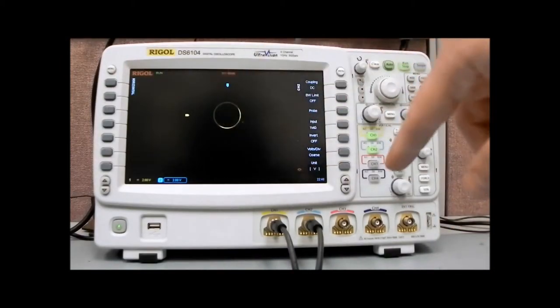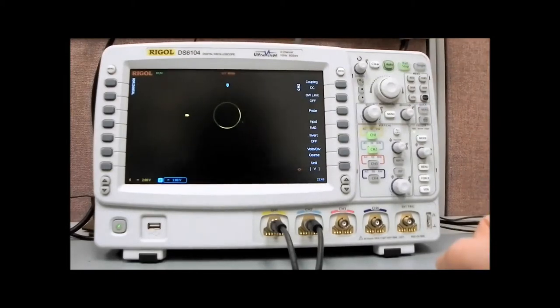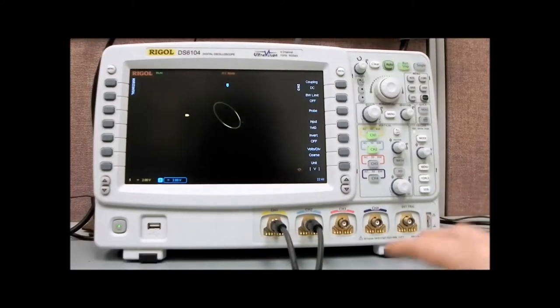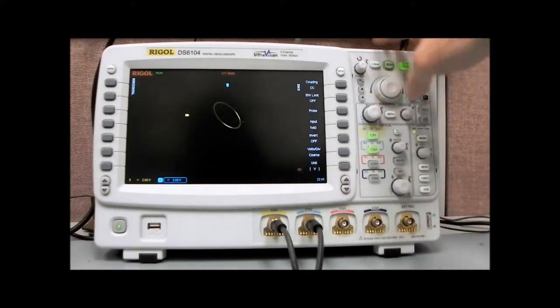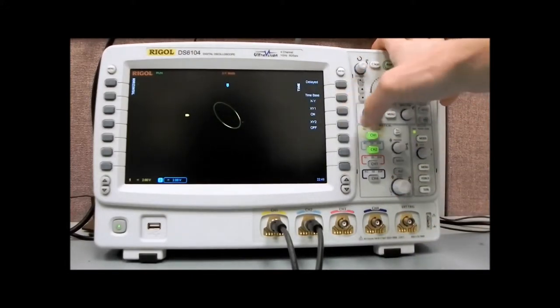So we're plotting X versus Y, and now we get the phase that's going to be a circle when they're 90 degrees out of phase. If we did something like 125 degrees out of phase, you'll see that will turn into an ellipse. So that can be very useful when you want to see the phase differential between two incoming signals. Again, that's the X versus Y mode.